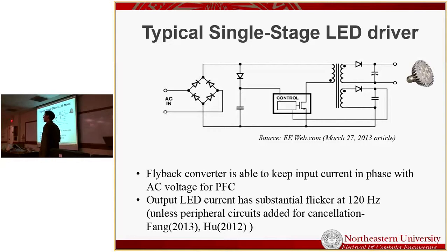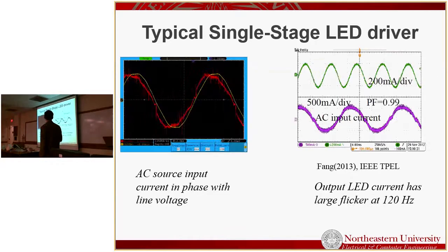It could also be done in continuous conduction mode, and you'd have multiple feedback loops going, so feed forward and feed back. And you get signals that would look like this for a single stage power factor correction. I've taken this from a scope and put it out of stage so you could see that they're not necessarily on top of each other. One is voltage and one is current. So there's a little bit of a phase lag here. So that's pretty good power factor correction. It's not great, but we could put that a little bit closer.